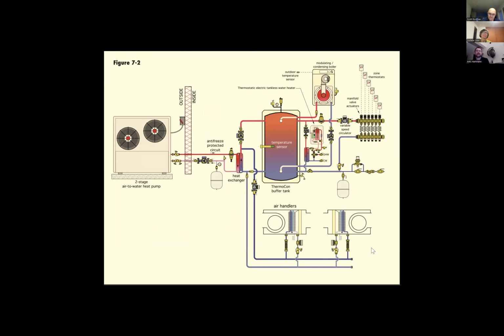So if the system gets installed in the attic, and imagine that the attic is not insulated, the rafters are not insulated, you just have it on the floor. The system itself is producing heat or cool, and the temperature running inside the ductwork in the attic, in the summer, is at 40 degrees. So it's very cool in the ductwork. The ambient air in the summer in an uninsulated attic is going to be over 100 degrees. Normally in physics, heat wants to go towards the cold. So with 100 degree air outside and 40 degree temperature in the ductwork, the ductwork is just not going to hold. You have insulation, which is great for the ductwork, but it's not enough to push away that 100 degree temperature attack towards the 40 degree temperature.